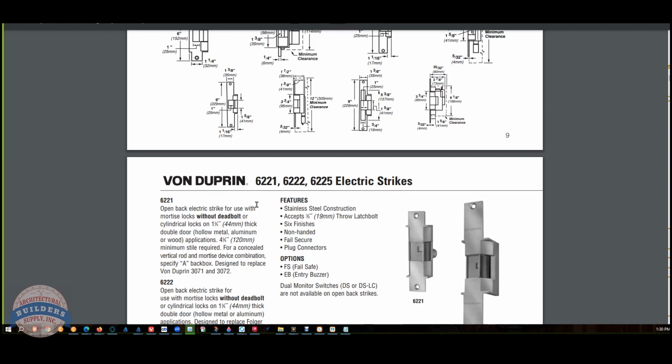Don't worry about free-swinging. But what's going to happen when there's a fire in the alarm panel? It's going to open the circuits, right? I realized that was wrong once I said it. You understand it, but let's just... In the absence of power, when the relays on the fire panel open that circuit, those strikes are going to be stone-cold locked. That's fail secure. Go back to your prison thing. It's awesome. Gotcha.